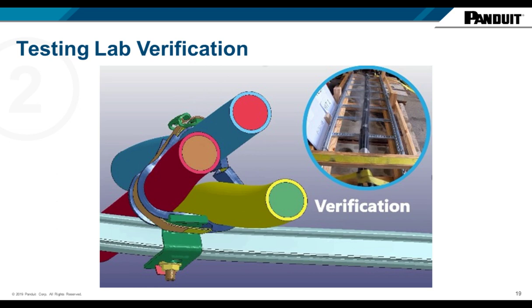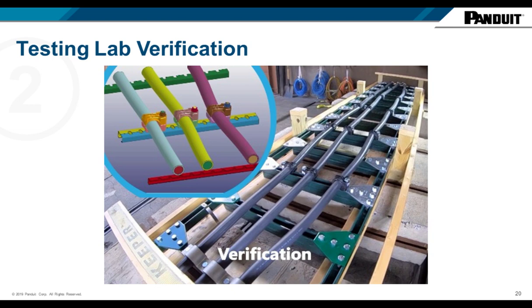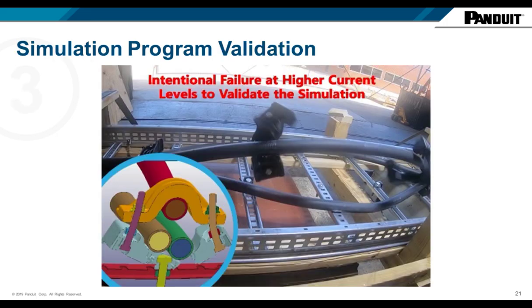In the testing lab verification process, you can see on the left our buckle strap cleat in an ANSYS simulation still shot, and in the upper right the test rig. We passed because the cleats did not come apart, and the subsequent DC current test after the short circuit event was successful. Here's one of the polymer one-hole cleats in both the ANSYS simulation and the test rig — we performed the simulation to the targeted kiloamp short circuit current rating and validated the process to get KEMA approval and IEC rating.